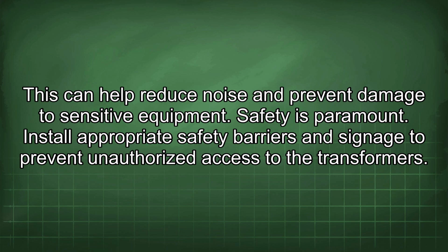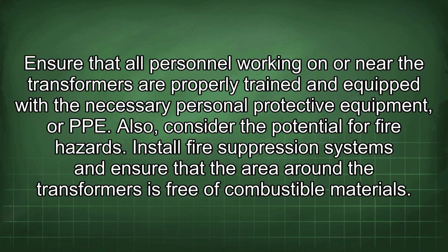Safety is paramount. Install appropriate safety barriers and signage to prevent unauthorized access to the transformers. Ensure that all personnel working on or near the transformers are properly trained and equipped with the necessary personal protective equipment, or PPE. Also, consider the potential for fire hazards. Install fire suppression systems and ensure that the area around the transformers is free of combustible materials.